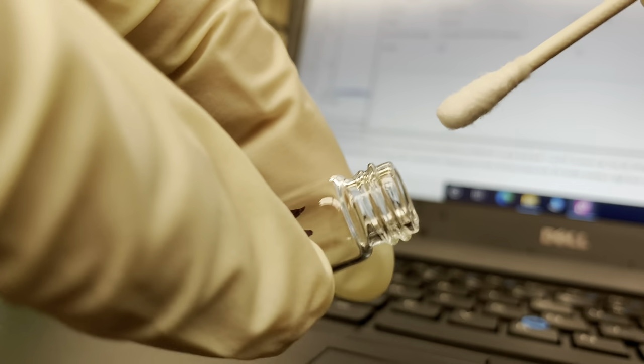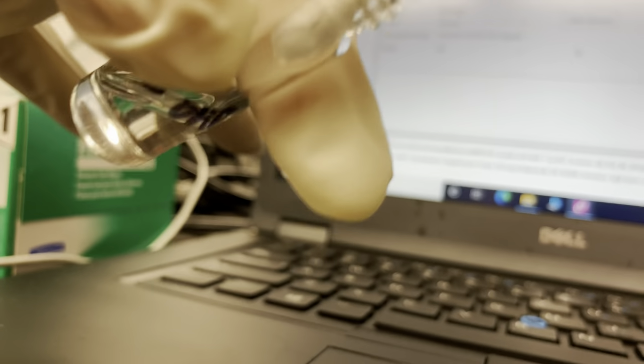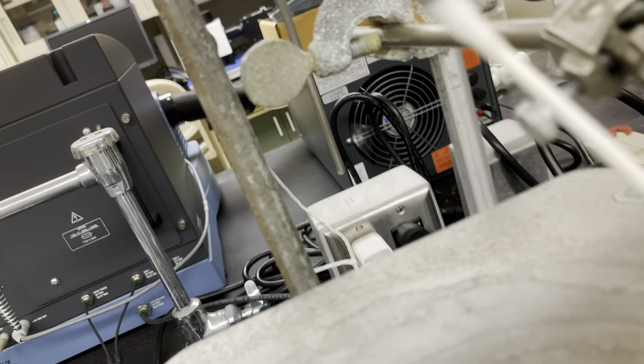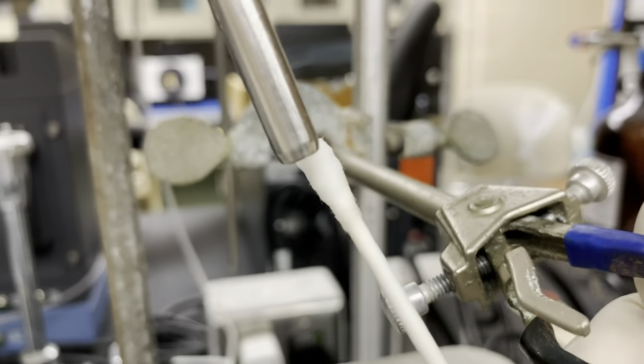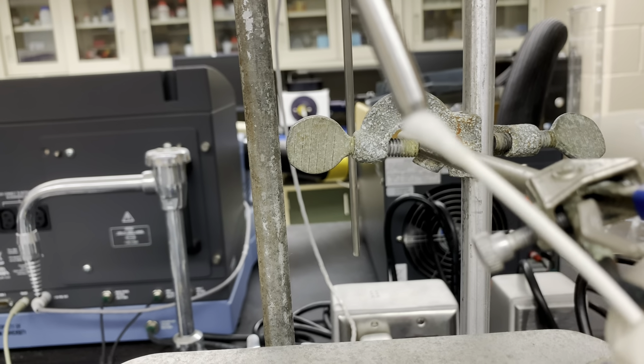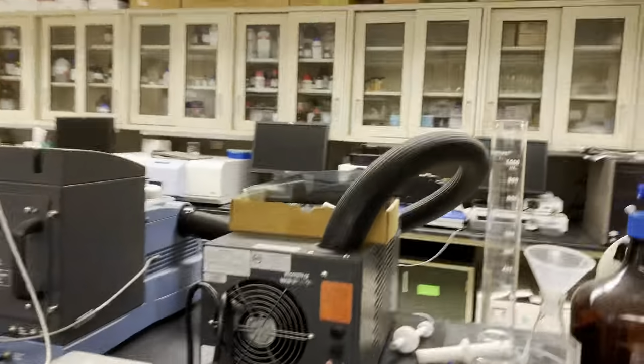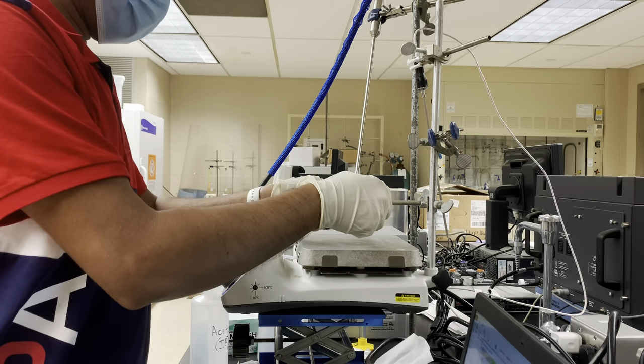Soak the probe tip with this acid solution using the cotton bud. Now again soak the probe tip with this cotton bud. It makes the tip of the probe saturated, because there is a small hole-type thing. If you immerse the probe inside the liquid and there is an air bubble, it might give you the wrong data. That's why we are making the probe tip saturated with that solution using the cotton bud.